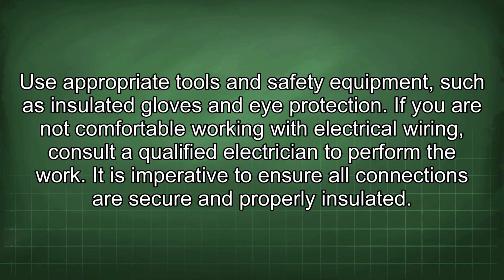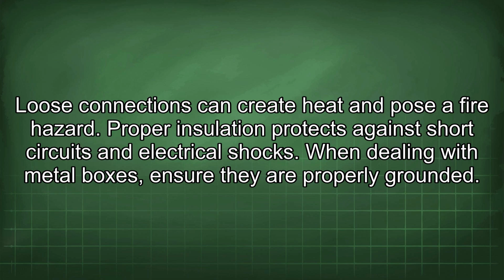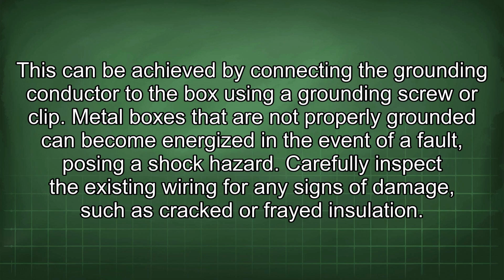It is imperative to ensure all connections are secure and properly insulated. Loose connections can create heat and pose a fire hazard. Proper insulation protects against short circuits and electrical shocks. When dealing with metal boxes, ensure they are properly grounded. This can be achieved by connecting the grounding conductor to the box using a grounding screw or clip. Metal boxes that are not properly grounded can become energized in the event of a fault, posing a shock hazard.